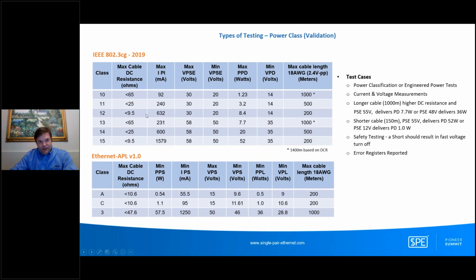So we have class 10 through 12. You can see that you can produce higher power, but the cable length gets shorter. So you have some loss in the cable. And of course, the higher power is delivered over shorter cables to the end device. Then we go to class 13 through 15, and you see the voltage increases from 50 to 58 volts.